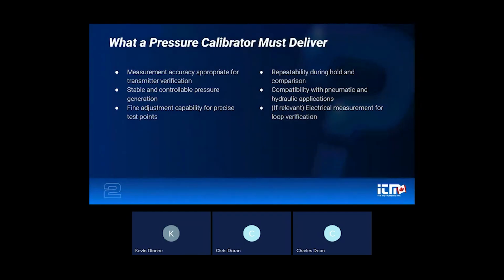If it's going to replace your traditional pump setup, it must provide measurement accuracy that is appropriate for the instruments being verified. So when calibrating transmitters or gauges in the field, the reference device must maintain a clear accuracy ratio so that overall measurement uncertainty remains controlled and defensible. Second, pressure generation must be stable and controllable. So it's not enough to simply reach a pressure value. The calibrator must allow fine adjustments so that test points can be approached gradually and held without overshoot or instability.